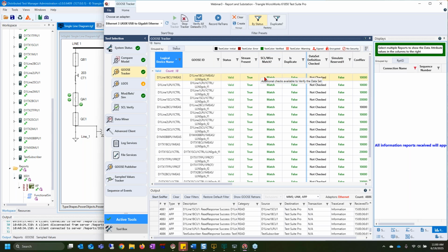For instance, there is missing an SCL. And what that means is that TSP has found a GOOSE stream on the network that you're looking at, but you have in no way informed it, by providing an SCL file, on what that GOOSE stream is. It'll let you know, hey, I found this GOOSE stream on the wire, and I don't know why it's here. It's not part of the SCL file. That could be you forgot to add the SCL file, or you've got to turn off a device for another testing scenario, or anything like that.